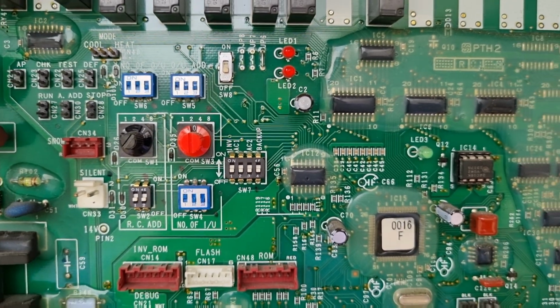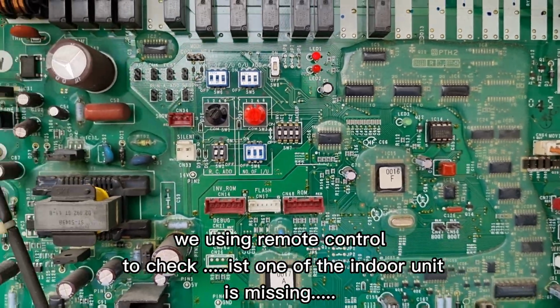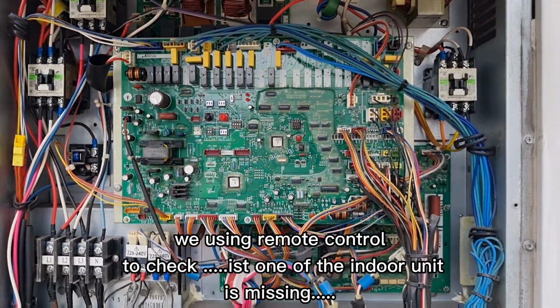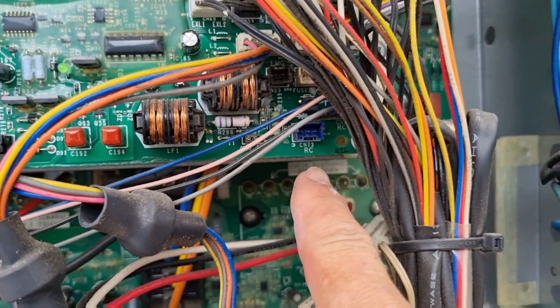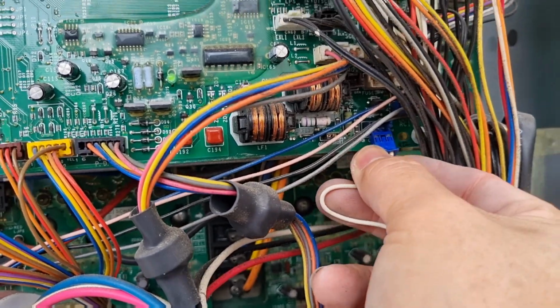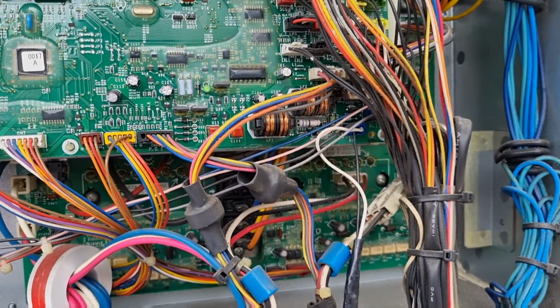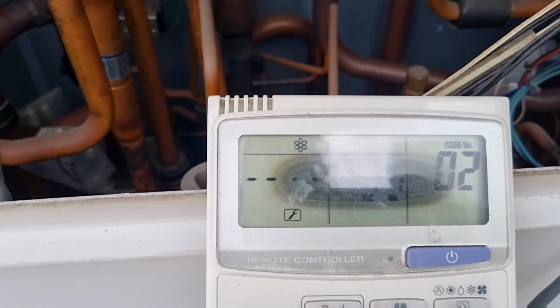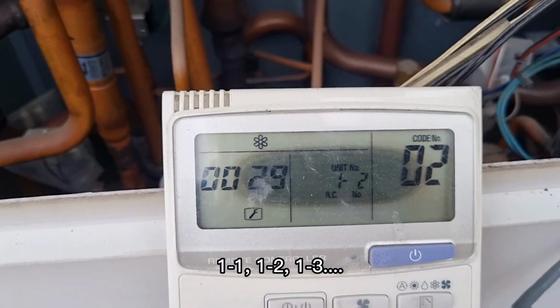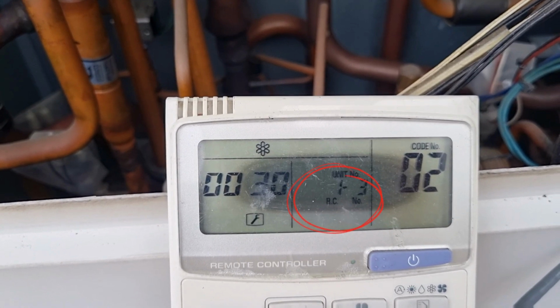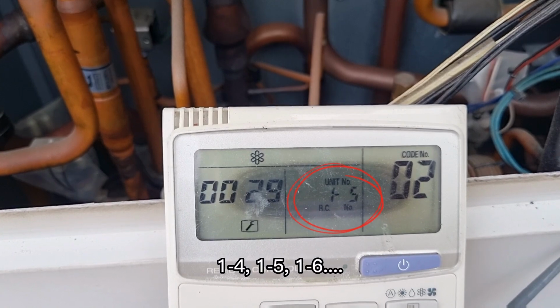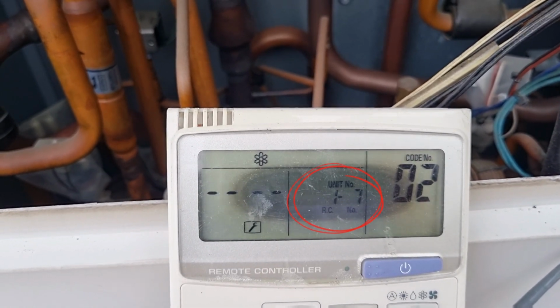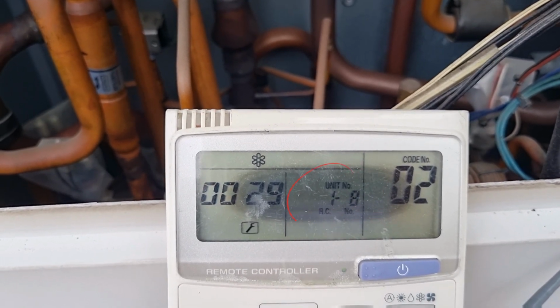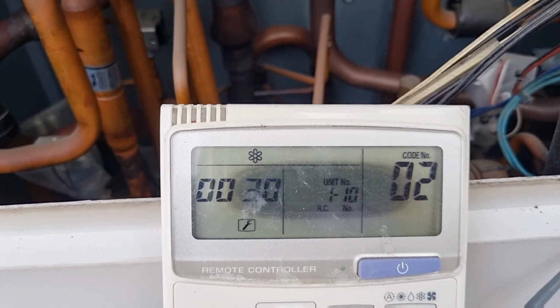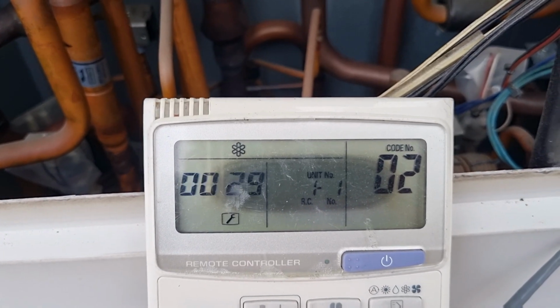We check the remote control. We use the wired remote control to check whether one of the indoor units is missing. Okay, RC, this is for remote control. Okay, the 0. The error E06. 1-1, 1-2, 1-3, 1-4, 1-5, 1-6, 1-7, 1-8, 1-9, 1-10. Okay, total 10 indoor units.